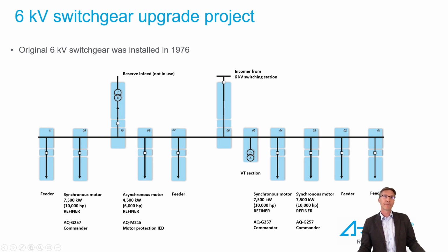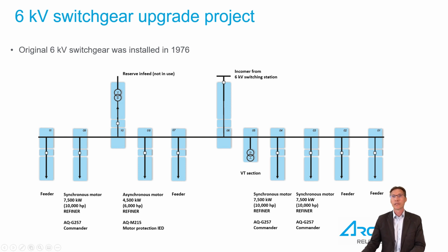Here is a simplified principal single line of the switchgear, originally installed back in 1976. You can see one incoming feeder fed from another 6 kV switching station. We have several large motors on this lineup. So you see 3 synchronous motors of about 8 megawatts or 10,000 horsepower. You see 1 asynchronous motor, also large, almost 5 megawatts or 6,000 horsepower. And all these are refiners. Then also feeders to the distribution of the system.